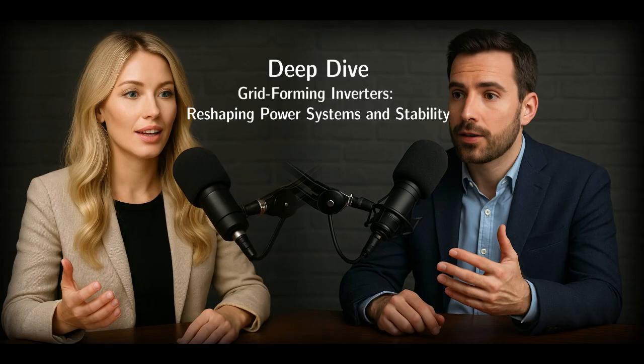Much lower, yes. And critically, they provide zero inherent inertia. Any frequency response they offer comes purely from programmed control algorithms reacting to grid measurements, not from physical energy storage. And they have no black start capability. They can't energize a dead grid. It really sounds like they were tailor-made for the old grid, the one dominated by synchronous generators. Why did they work so well in that context? They worked because the synchronous generators did all the heavy lifting for stability.